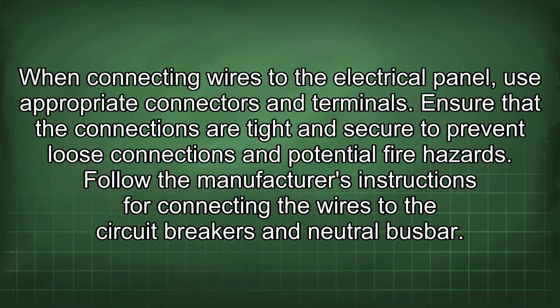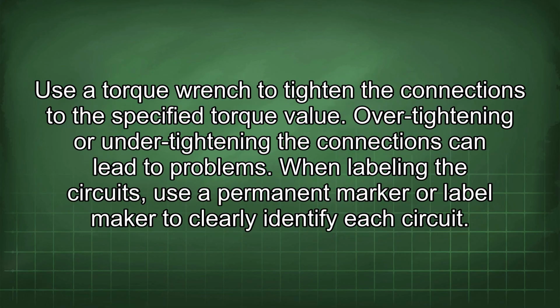When connecting wires to the electrical panel, use appropriate connectors and terminals. Ensure that the connections are tight and secure to prevent loose connections and potential fire hazards. Follow the manufacturer's instructions for connecting the wires to the circuit breakers and neutral busbar. Use a torque wrench to tighten the connections to the specified torque value. Over-tightening or under-tightening the connections can lead to problems.